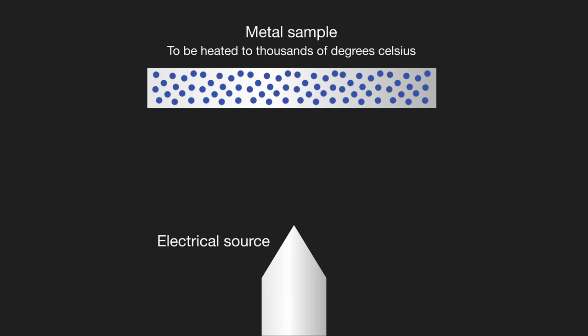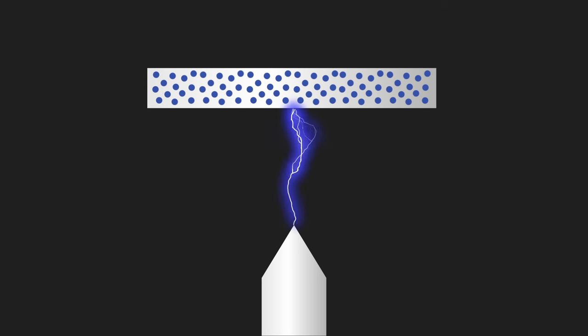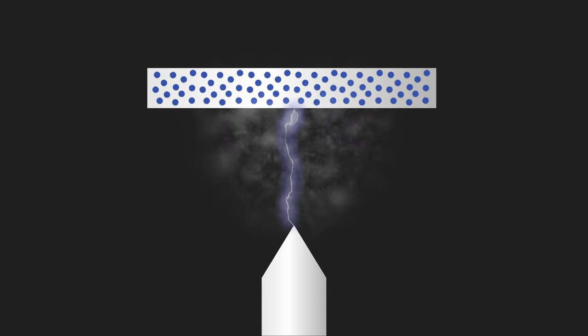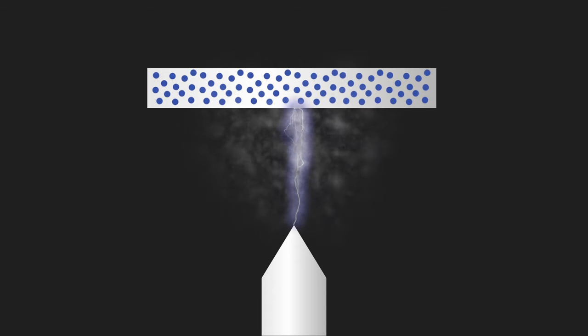This is done using an electrical high voltage source in the spectrometer via an electrode. The difference in electrical potential between the sample and electrode produces an electrical discharge. This discharge passes through the sample, heating and vaporizing the material at the surface and exciting the atoms of the material, which then emits the element characteristic emission lines.